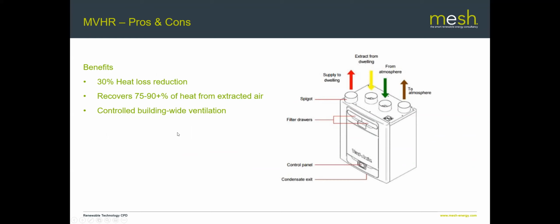and it provides controlled, and that's the main thing, controlled building wide ventilation. So one of the things with natural ventilation is that it is affected by the whims of the weather, because if you've got a particularly blustery day and it happens to be blowing at the wall which has got a lot of the ventilators in, you'll get a greater level of ventilation than you will on a still summer's day, where the air is not moving through those ventilators with the action of the wind.